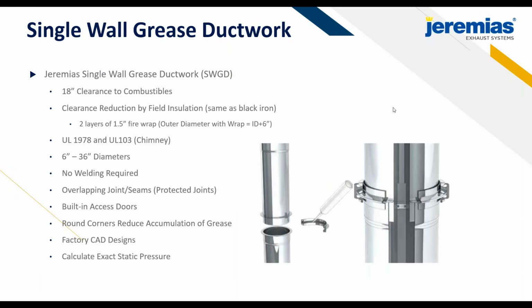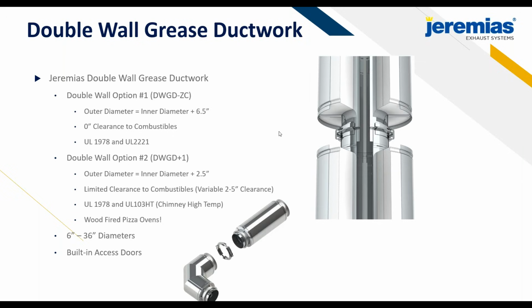So Jeremias is a manufacturer that we rep. They are a German-based manufacturer. They have a plant in Atlanta as well. They do round grease duct. They also do some chimney duct and flue stuff as well. But for now, we're just going to be focusing on the grease ductwork. So typical is 18-inch clearance to combustibles. We can do double wall or single wall. Right now, we're just looking at single wall. As we go into double wall as well, it's the clamp style mate together ductwork.